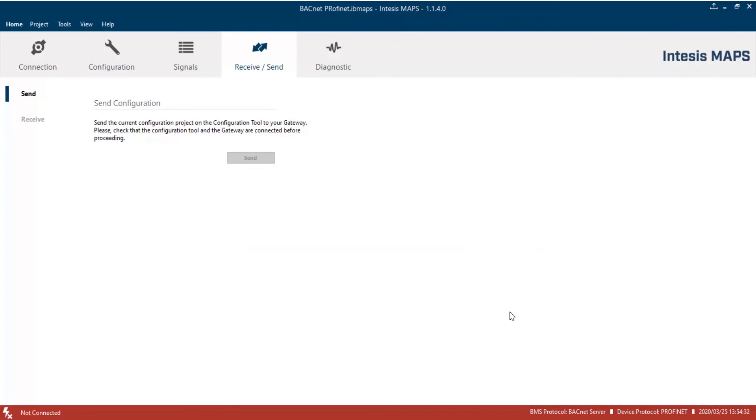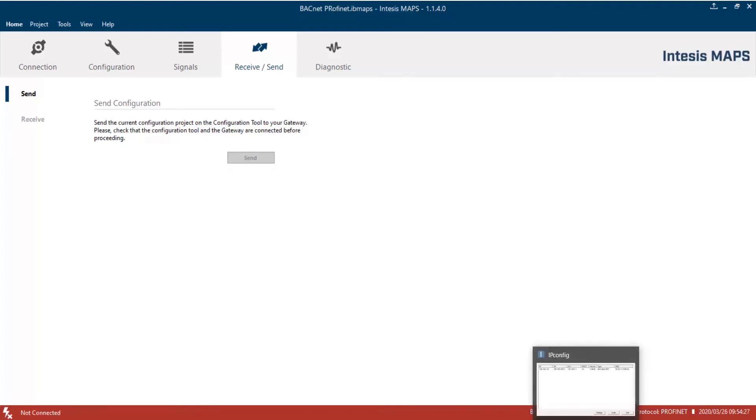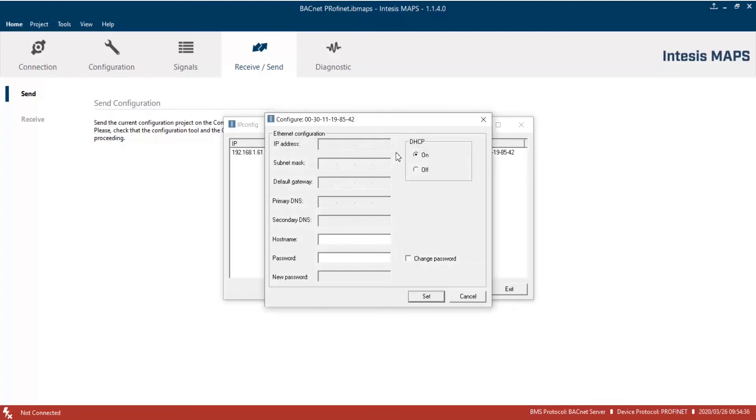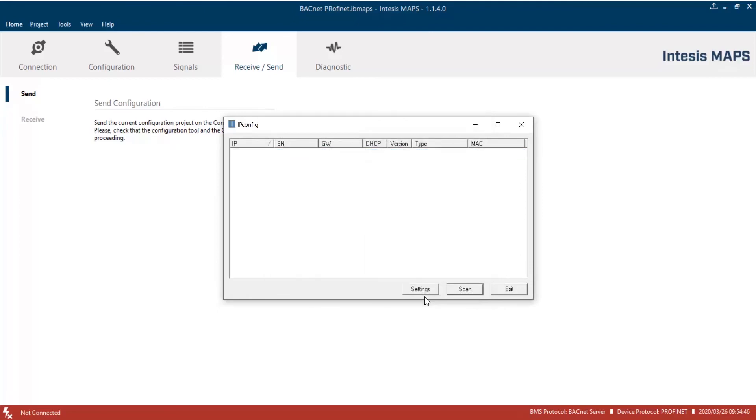Now, we can start to configure Profinet interface. To do so, we will use the ipconfig tool which uses DCP protocol to discover devices and set their configuration. So, let's start ipconfig and then click scan button. Finally, double click on Intesis Gateway. Here, select the right configuration for the Profinet interface and set all required parameters. Finally, click on set to save configuration on the gateway.